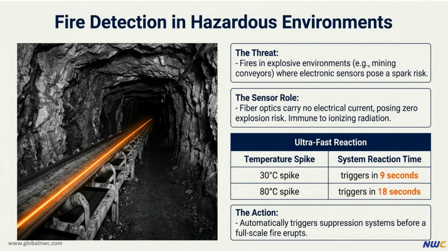In high-risk, explosion-proof environments such as mining conveyor systems, even a tiny spark can lead to a catastrophic accident. For this reason, fiber optic sensor technology, completely free from electrical spark risks, has emerged as an essential alternative. This system is immune to ionizing radiation and demonstrates exceptional response speed, detecting rapid temperature increases to 30 degrees Celsius and 80 degrees Celsius within just 9 and 18 seconds, respectively. By triggering an automatic fire suppression system before flames can spread, it provides an optimal safety solution designed to prevent major industrial accidents before they occur.